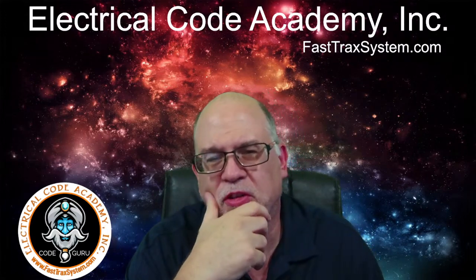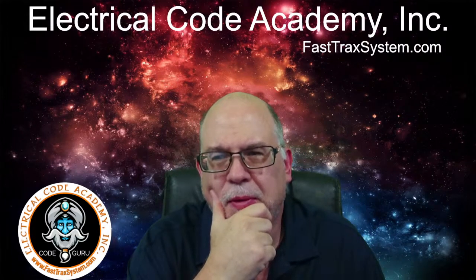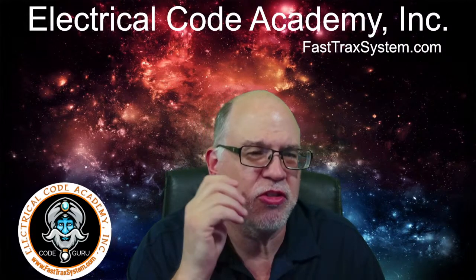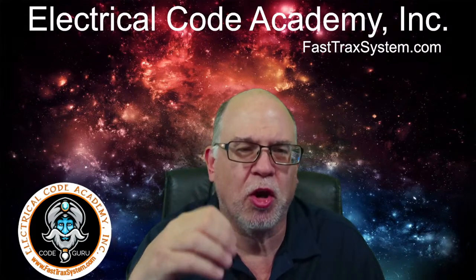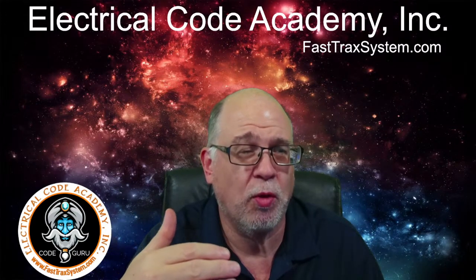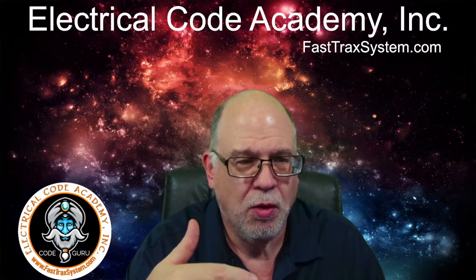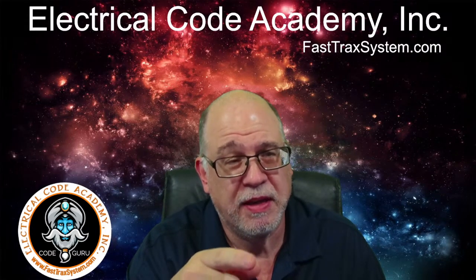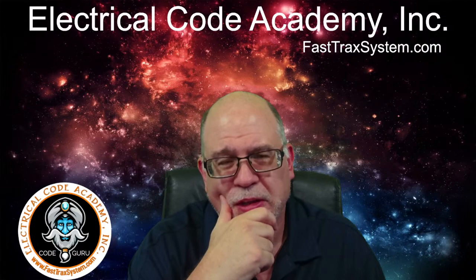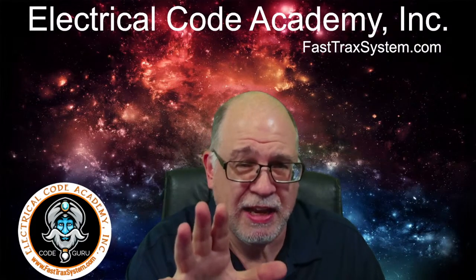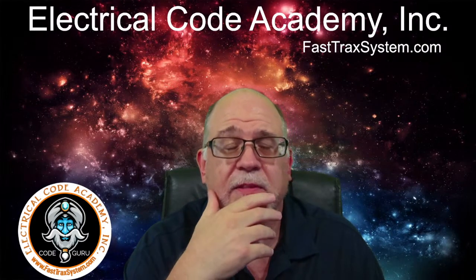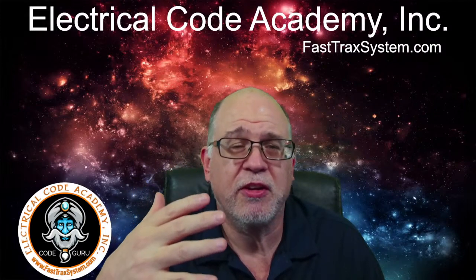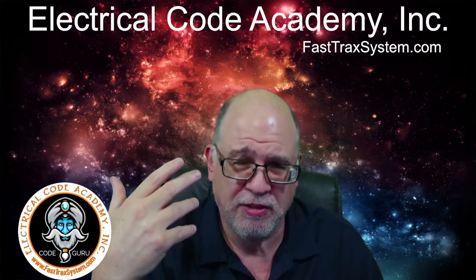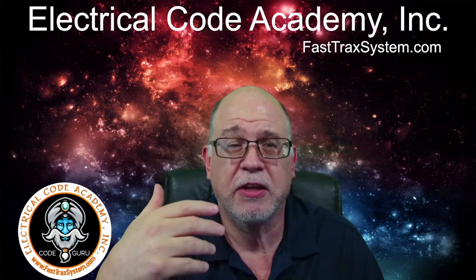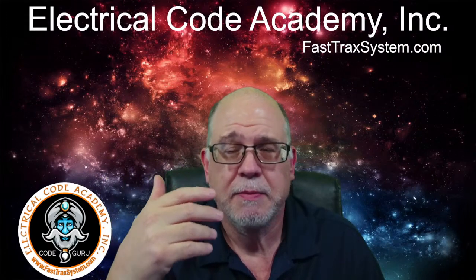Now, in my Fast Trax program, usually I teach a certain way because I know what the code panel's intent was, even though it's lost in translation. I'm going to show you what I mean tonight, because I usually teach that when you're doing the neutral, some of you might remember, when you're doing ranges and dryers, you get to apply 70%. That's in 220.61(B).